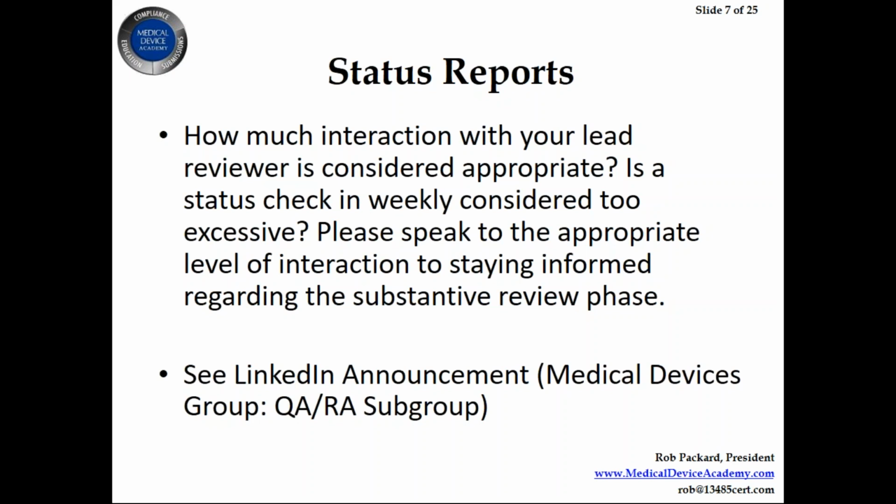But I explained that it depends a little bit whether you're working with the FDA or you're working with a CE marking technical reviewer. If you're working with the FDA, the FDA does not want you to call them or email them to ask the status of a submission ever. They do not want you to do this. They specifically say they don't want you to do this. The process is very well defined. They have a guidance document for it.